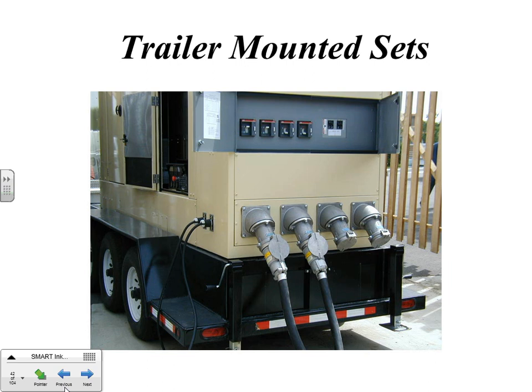Another thing that cities will be doing, they have a multiple voltage need. These are sold primarily to municipalities. These two little plugs here are for the water jacket heater and a battery charger. This particular unit sits as a standby at a particular site, so it'll operate totally as a standby emergency generator most of the time. If there's a situation where there's a widespread outage, these can be pulled out, and the unit can be taken to any one of a number of lift stations. And behind the door here, there's a voltage selector switch, so we could probably go from 120/208, 120/240, or to 277/480 just by changing that switch. It's very common for municipalities. It's a handy setup for them.